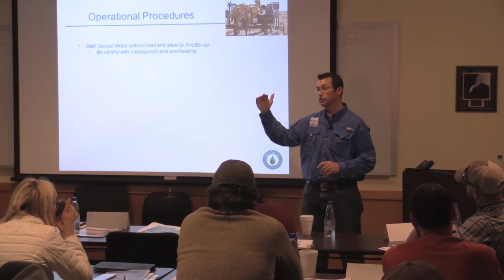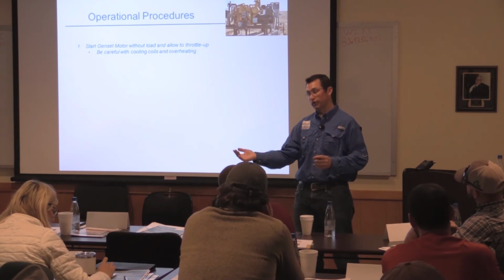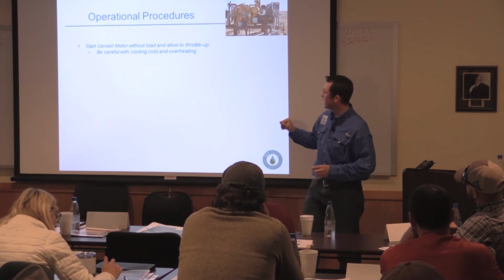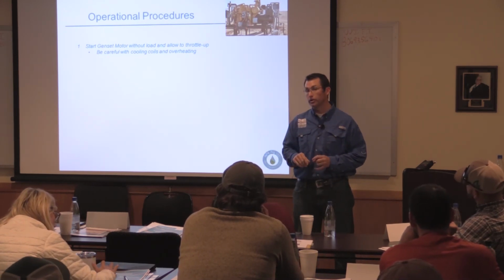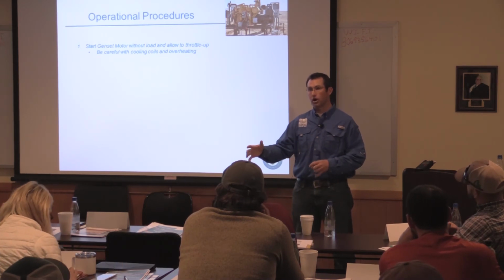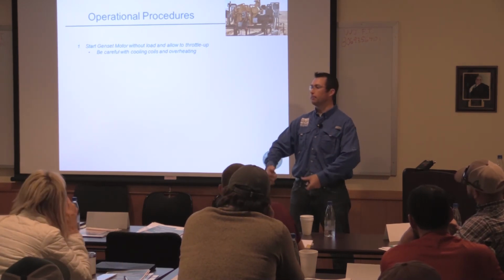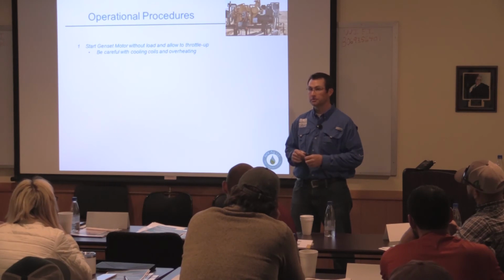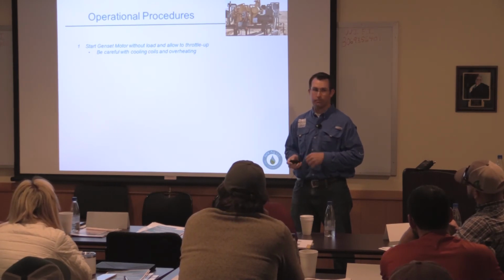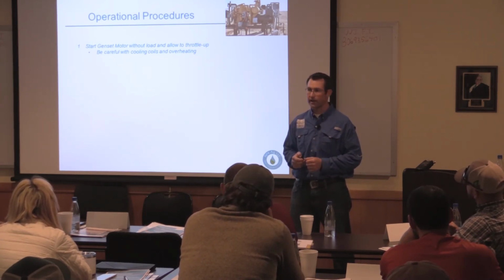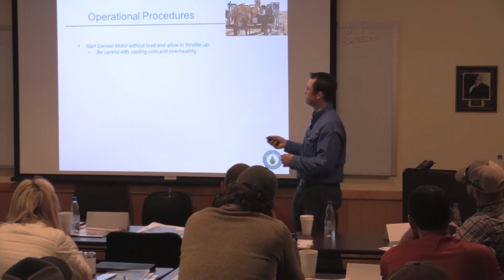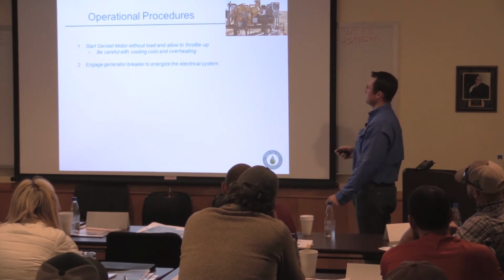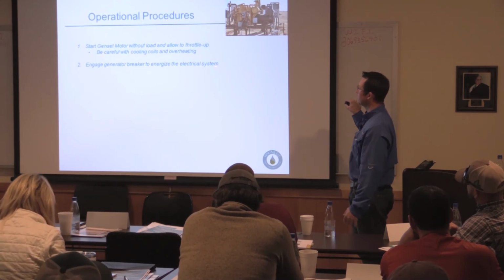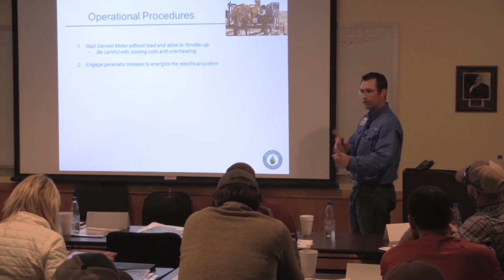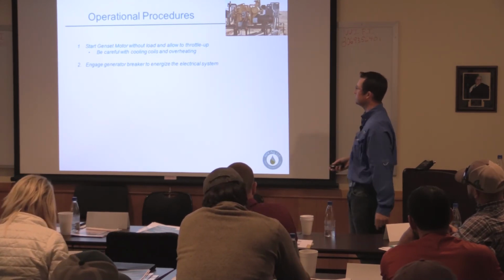Okay, you're not always going to be able to do that on your well because, for example, this is one of the reasons why you might want a radiator rather than cooling coils. You go out there, you can start it, warm it up with a radiator, you don't have to worry about pumping water yet. Or if you've got cooling coils, you better start getting water to the top really quick, just like you would have to with a natural gas scenario. Okay. The next step is to engage the generator breaker to energize the electrical system. So you got power from the generator, now you're going to engage the electrical system.